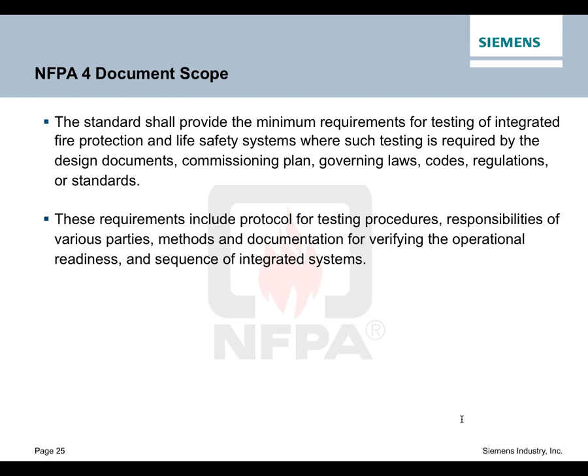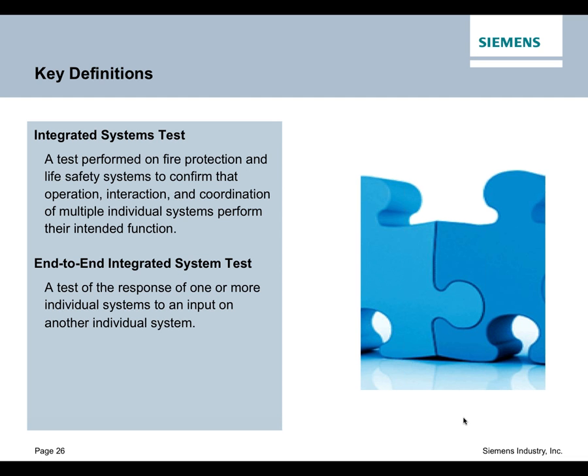You'll see that the scope of the document is pointed out here. The standard shall provide the minimum requirements for testing of integrated fire protection. What's important to understand here, and this can get confusing, I do sit on this technical committee, but I do not speak for NFPA. It was confusing as this was being identified, but this is not affecting the testing of the individual system. For that fire sprinkler system, you still test per NFPA 25. For the fire alarm system, you still test per NFPA 72. But when it comes to making sure that these systems all work well together and do what they're supposed to across all lines, that's when NFPA 4 is followed and applied.